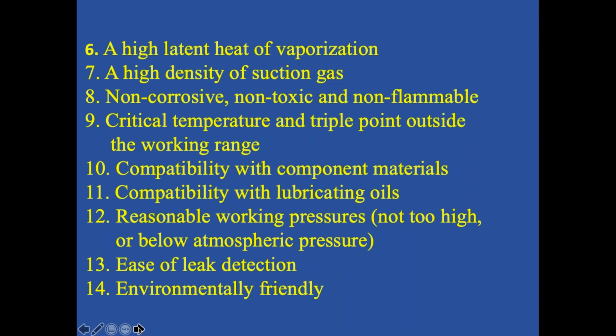Then it should have a high density of suction gas, because then your equipment will become compact. Your mass flow rate and volume flow rate will be reduced. The refrigerant should be non-corrosive, non-toxic, and non-flammable. The next important point is critical temperature and triple point, and these should be out of the working range. That means the critical temperature should be high and the triple point should be low. For our normal operating range in refrigeration and air conditioning, let us say from minus 40 degrees centigrade to plus 40 degrees centigrade is an average range. Besides this, we go for very low temperature applications, but those are rare. 95% of projects are covered in this range. And therefore, the critical temperature has to be higher than 40 degrees centigrade, and the triple point has to be much lower than minus 40 degrees centigrade.